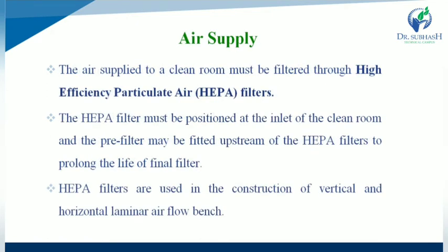Next one is air supply. The air supply to a clean room must be filtered through a HEPA filter, that is a high efficiency particulate air filter. So for maintaining an aseptic area, HEPA filters are used for air supply. HEPA filters must be positioned at the inlet of the clean room and a pre-filter may be fitted upstream of the HEPA filters to prolong the life of the final filter.